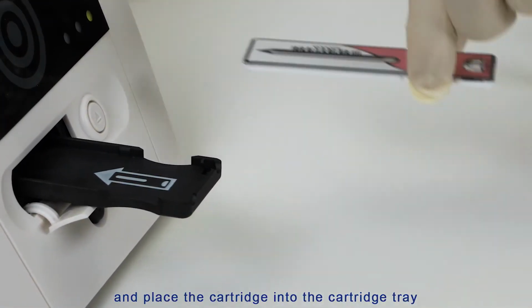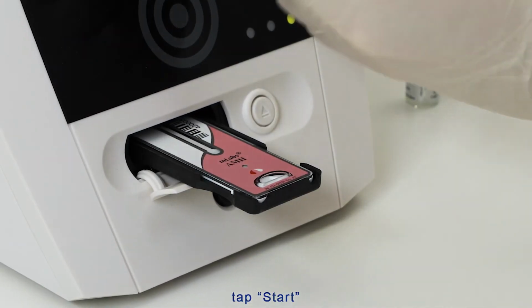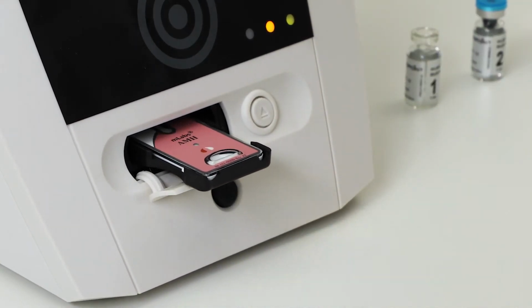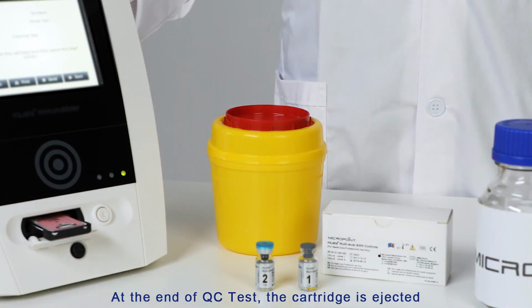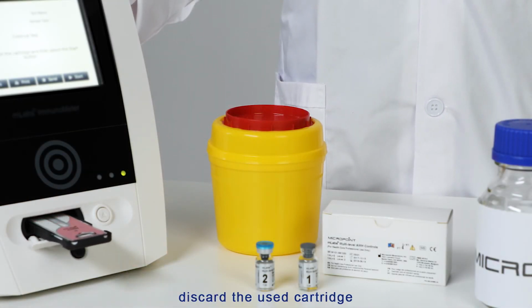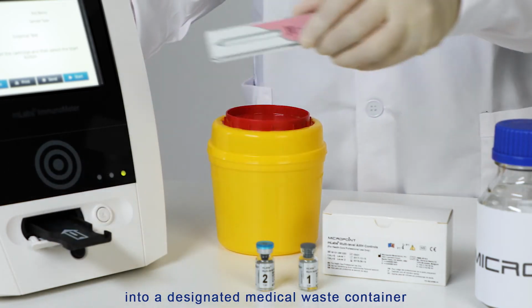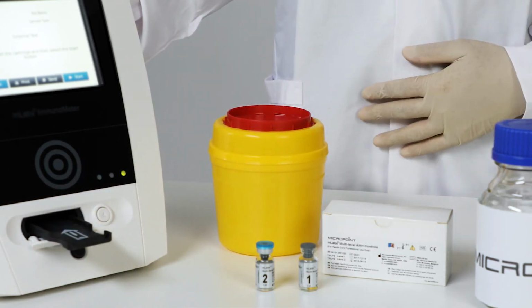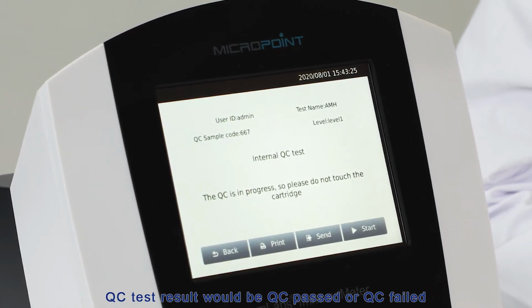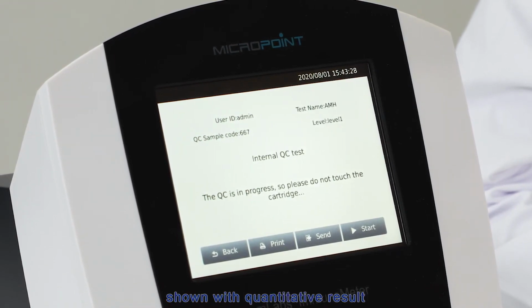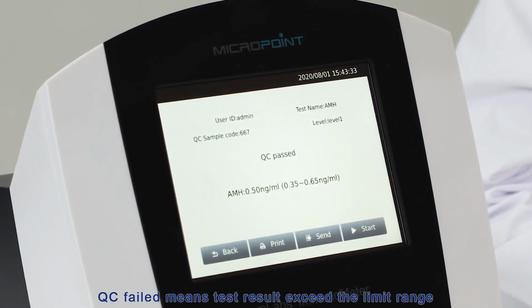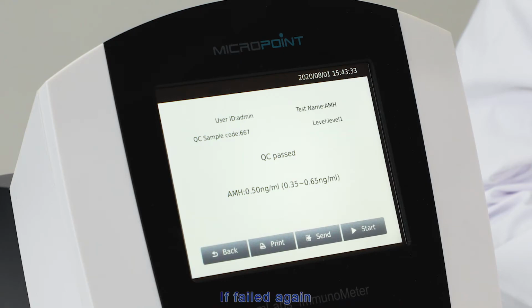and place the cartridge into the cartridge tray. Tap Start. QC test runs automatically. At the end of the QC test, the cartridge is ejected. Discard the used cartridge into designated medical waste container. QC test result will be QC passed or QC failed, shown with quantitative result and lower and upper limit. QC failed means test result exceeds the limit range. You need to repeat the QC process. Pay attention to every detail of the operation. If failed again, please contact your Micropoint distributor for further information.